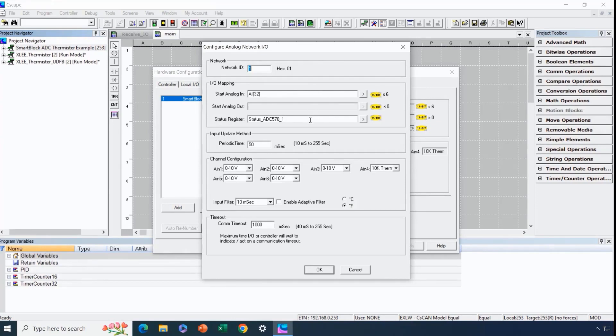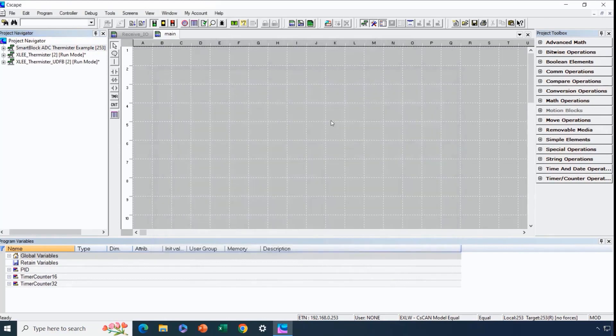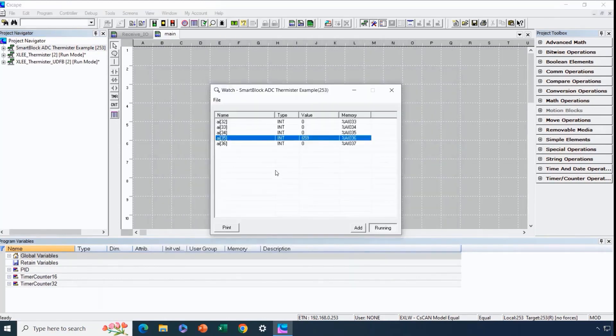AI32 as an array correlates to %AI33 as a real-world analog input memory register, and there are six consecutive analog input values reported by the smart block. We've also assigned a status variable, which is important to monitor the health of any remote I/O block. On the six channels, for channel number four only, we've selected a 10K thermistor as the input and degrees Fahrenheit, with values reported in tenth-degree increments. That's all that's required for the configuration. Looking at the data watch, we can see the raw data coming back from the smart block — channel four shows 65.9 degrees Fahrenheit, because it's giving an integer value of 659.